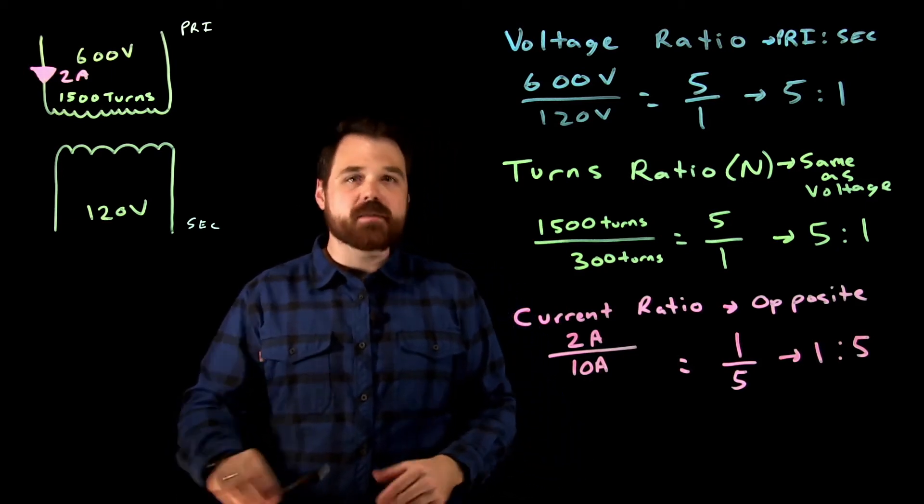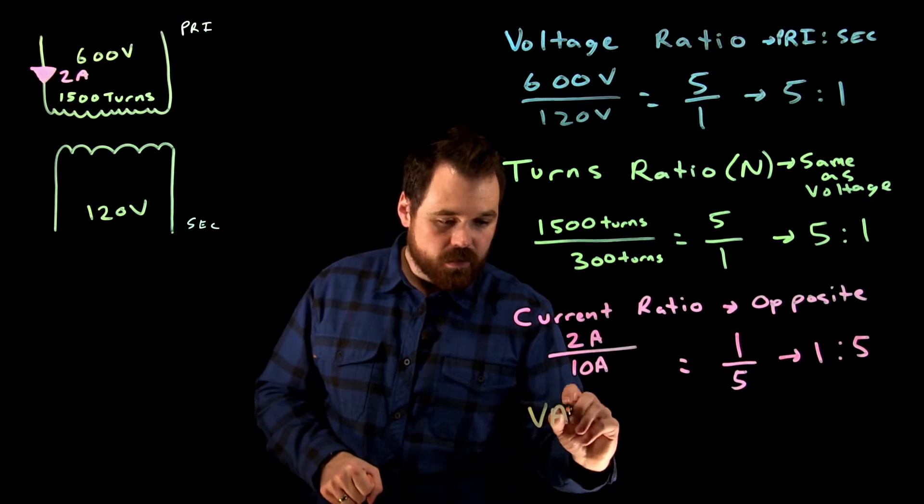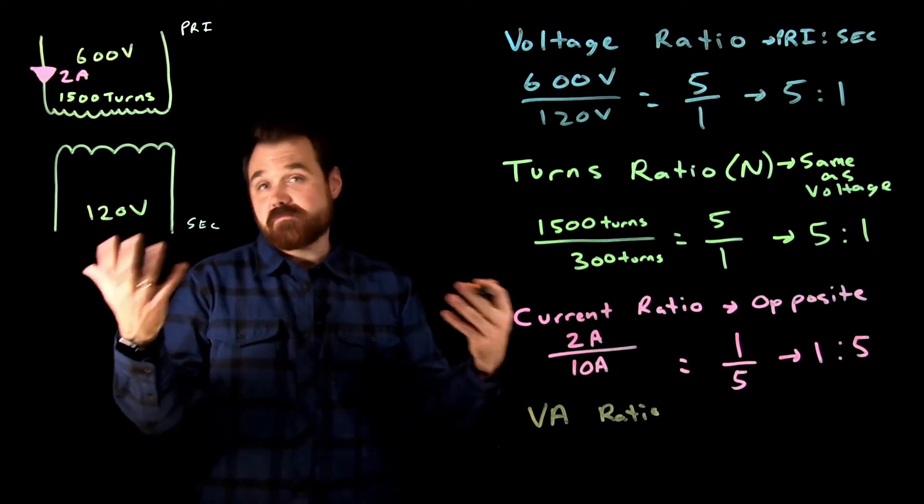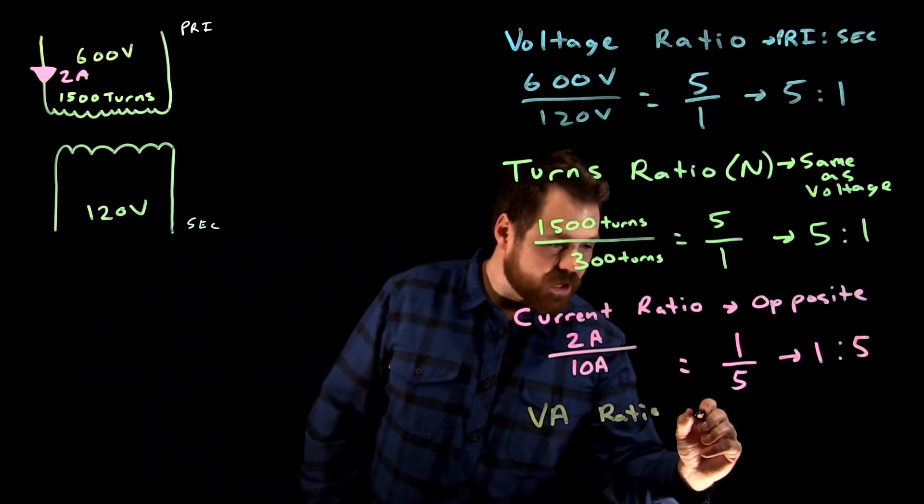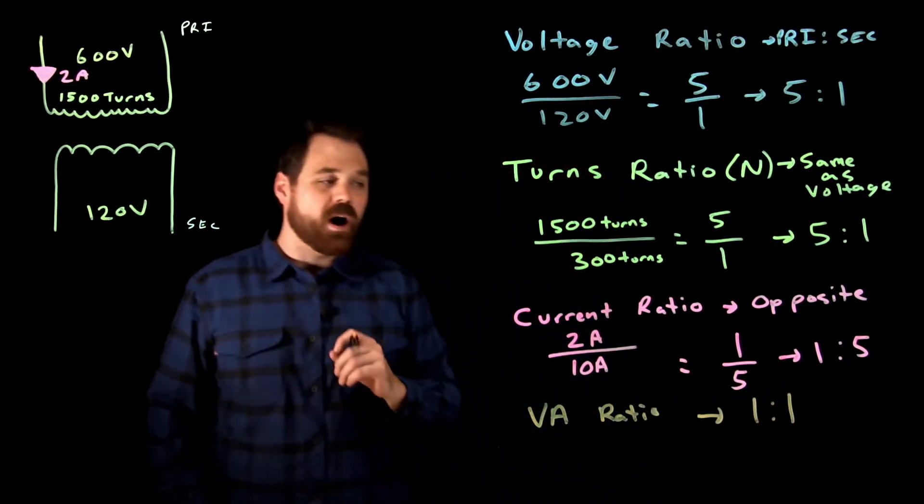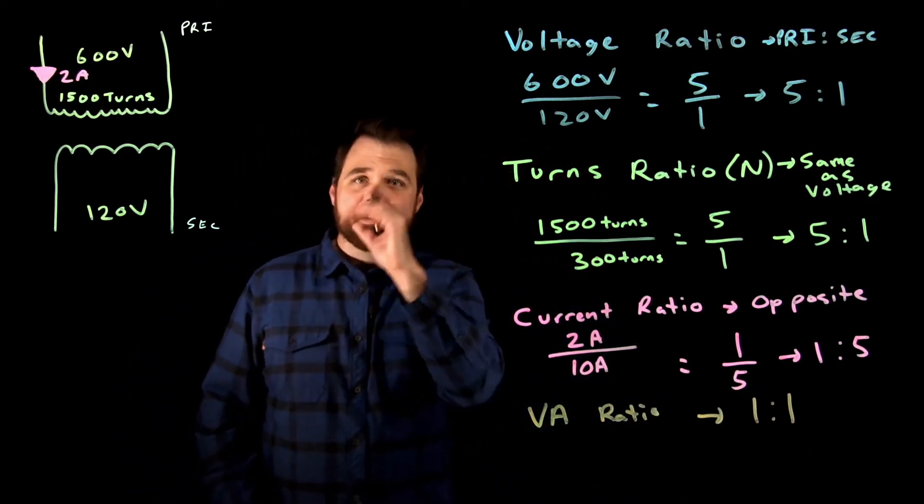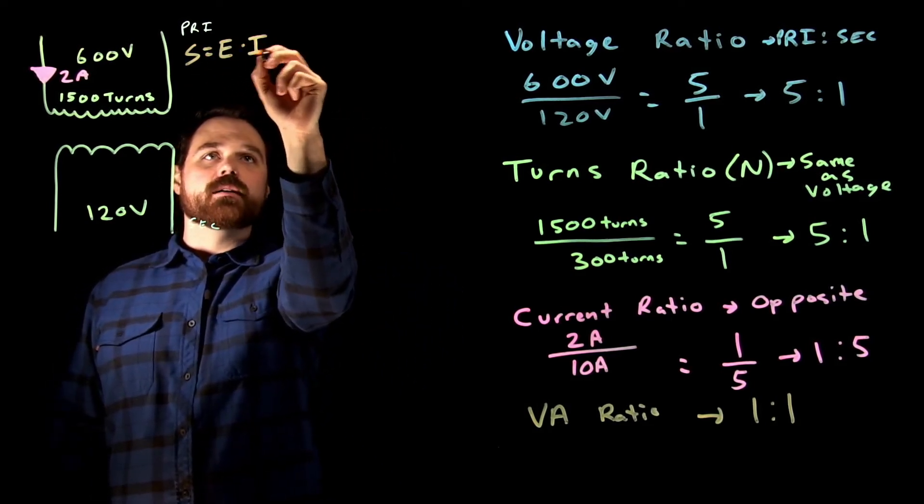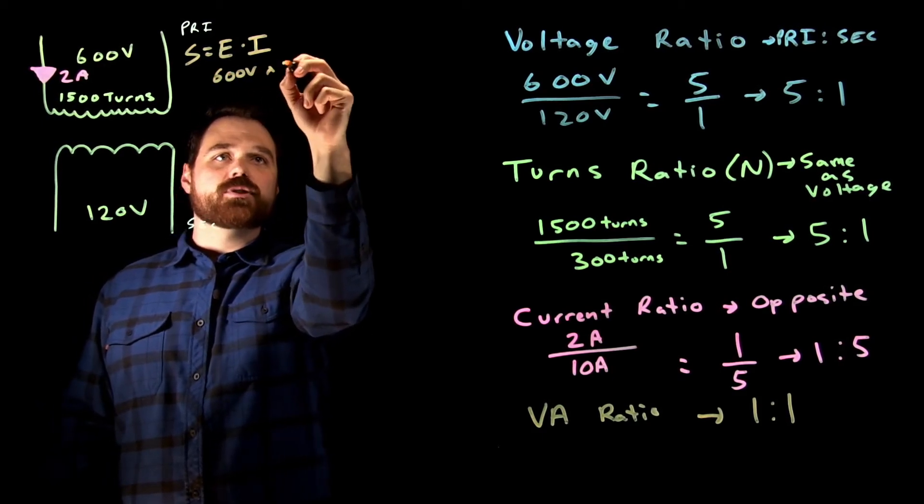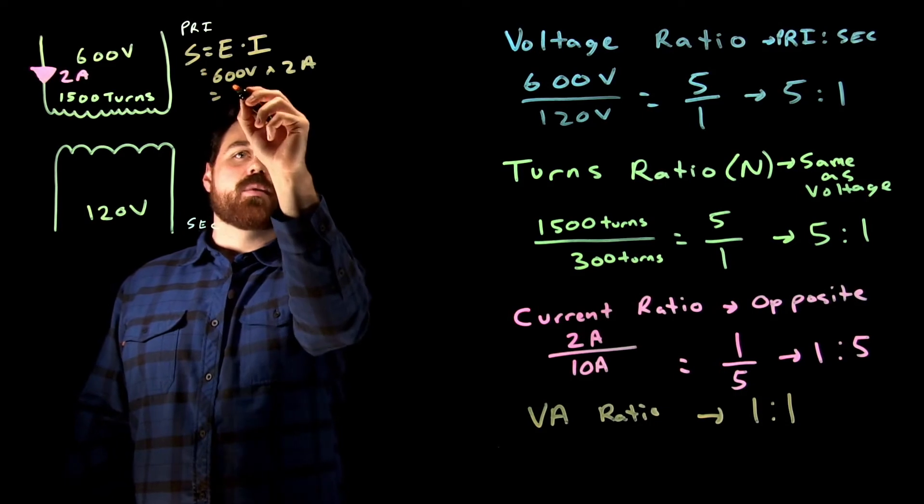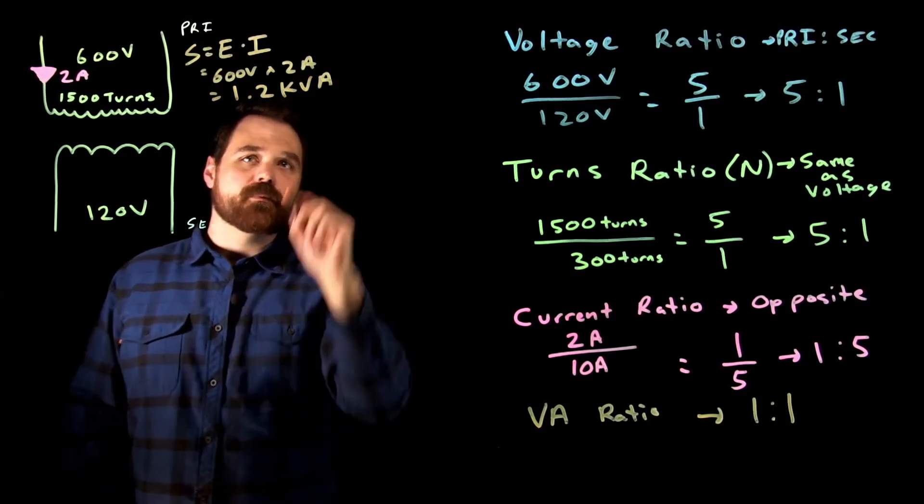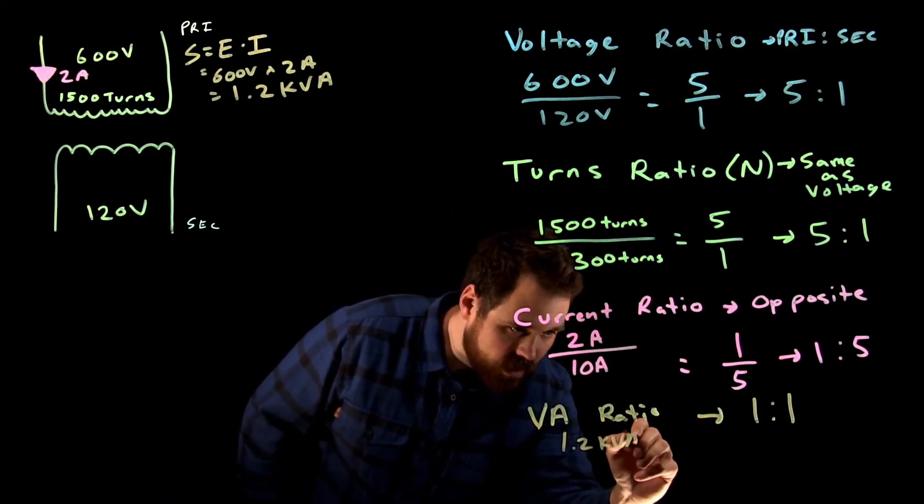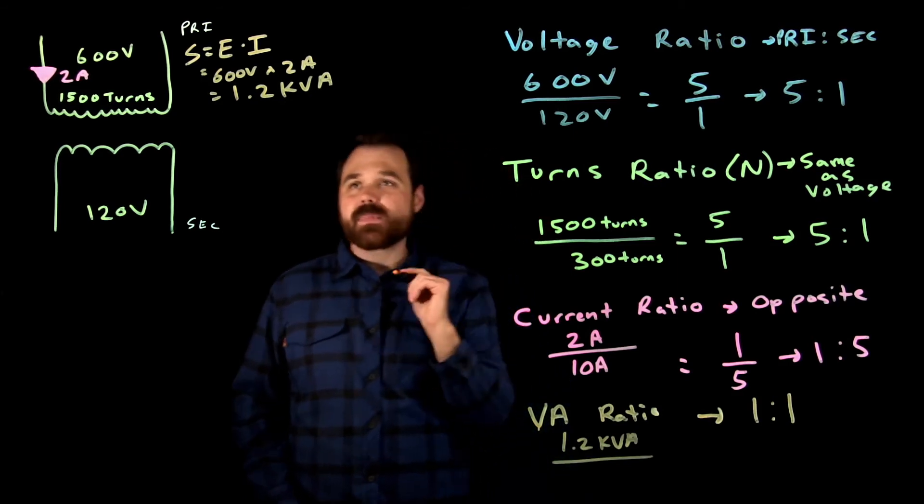Now the very last ratio I want to talk about is the VA ratio. Now the VA ratio in a perfect transformer, in ideal, in theory, in an ideal world is always going to be a one to one ratio. So let's talk about that. So let's talk about the primary first. So primary, S equals E times I. So we had 600 volts times two amps. That gives us 1.2 kVA, 1200 volt amps or 1.2 kVA. That's the primary.